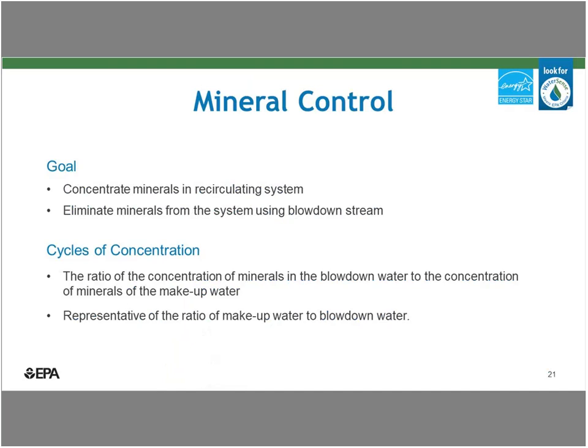So to improve water efficiency of your cooling tower, the goal is really to concentrate minerals in the recirculating system. As the mineral concentration rises, the blowdown stream will bleed off a certain amount of water and replace it with city water, thus reducing the overall concentration of the minerals in the system. This measure of efficiency is called cycles of concentration. It's a measure of the concentration of minerals in the blowdown water to the concentration of minerals in the makeup water. It's also representative of the ratio of the makeup volume to the blowdown water. So the higher the cycles, the less blowdown you'll have occurring.